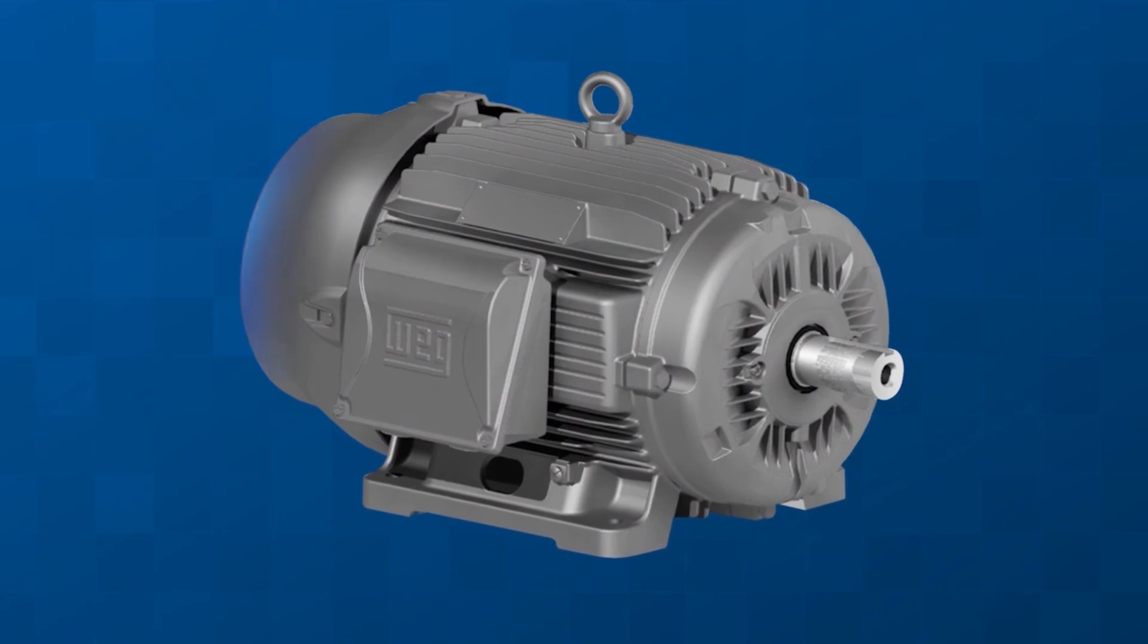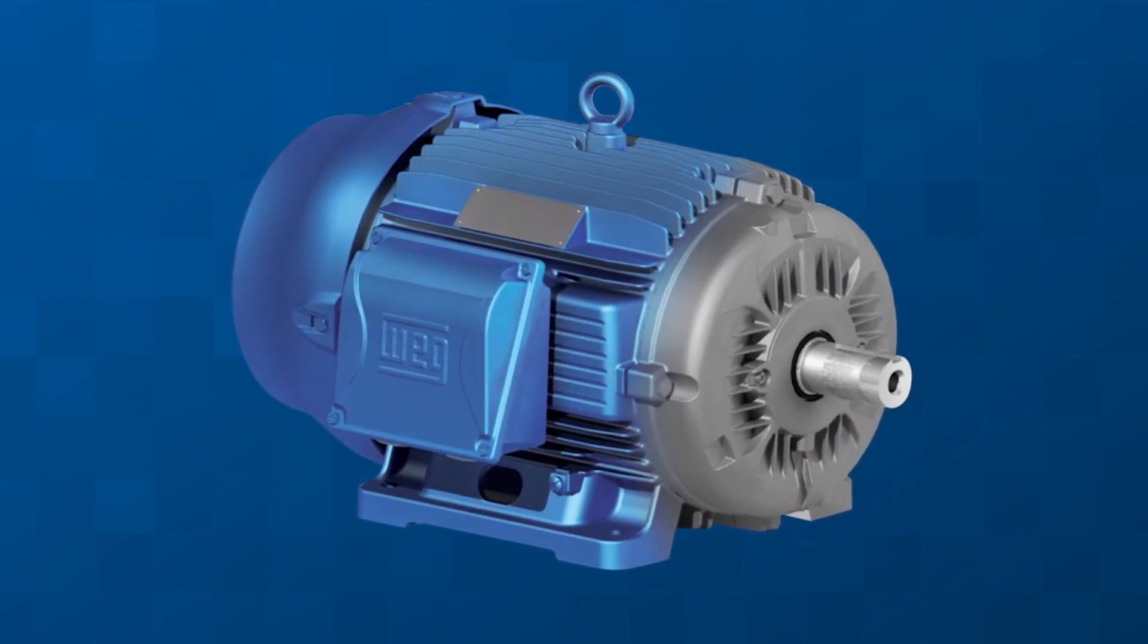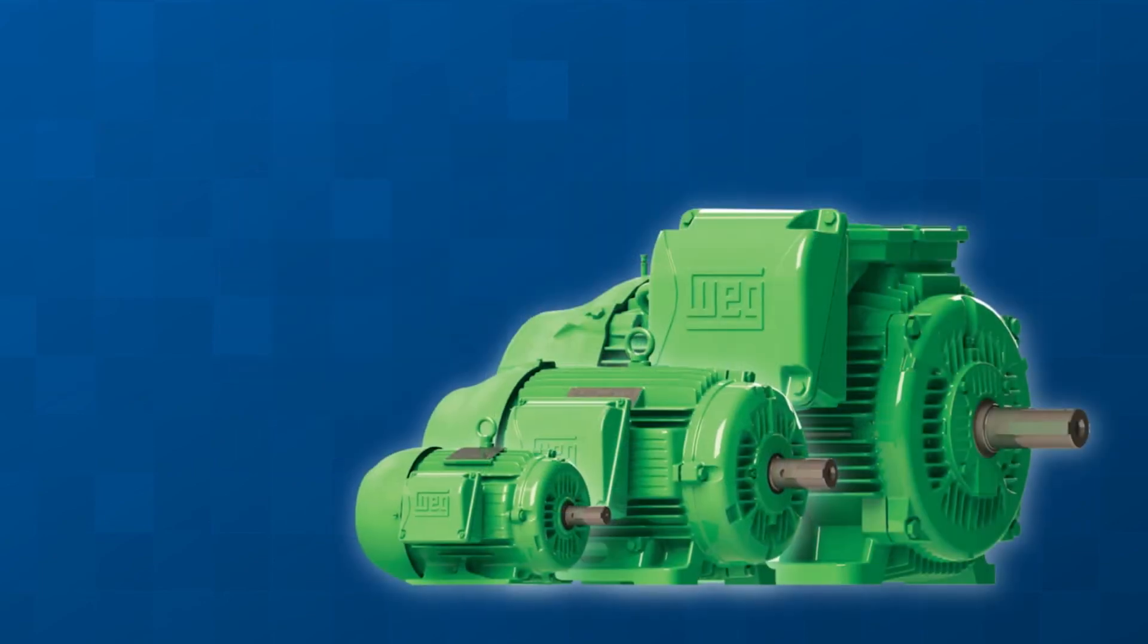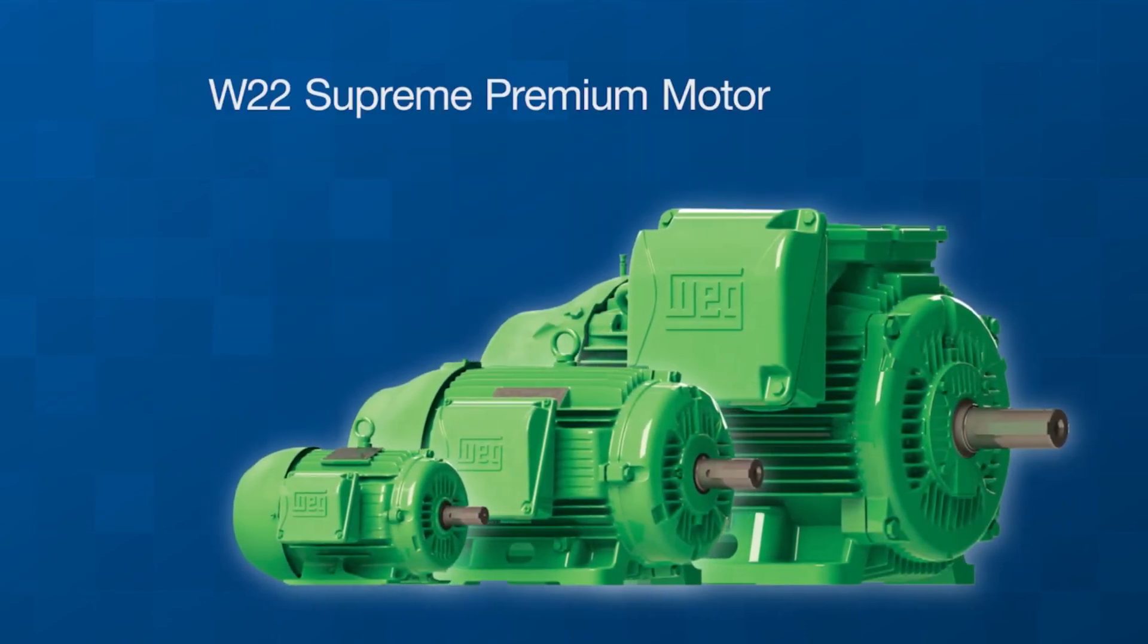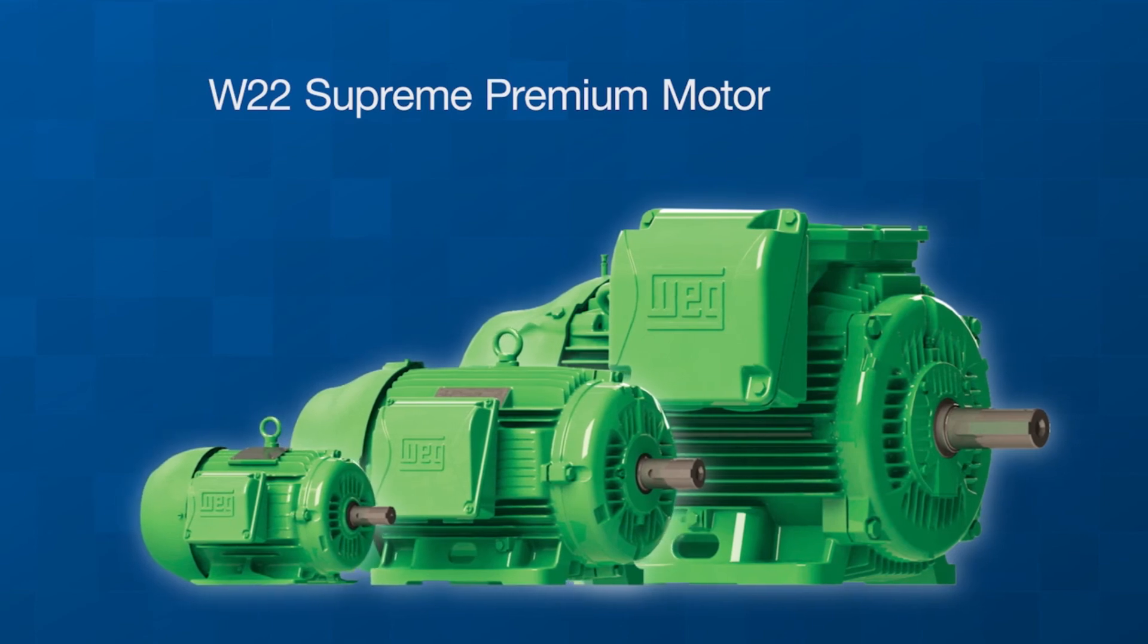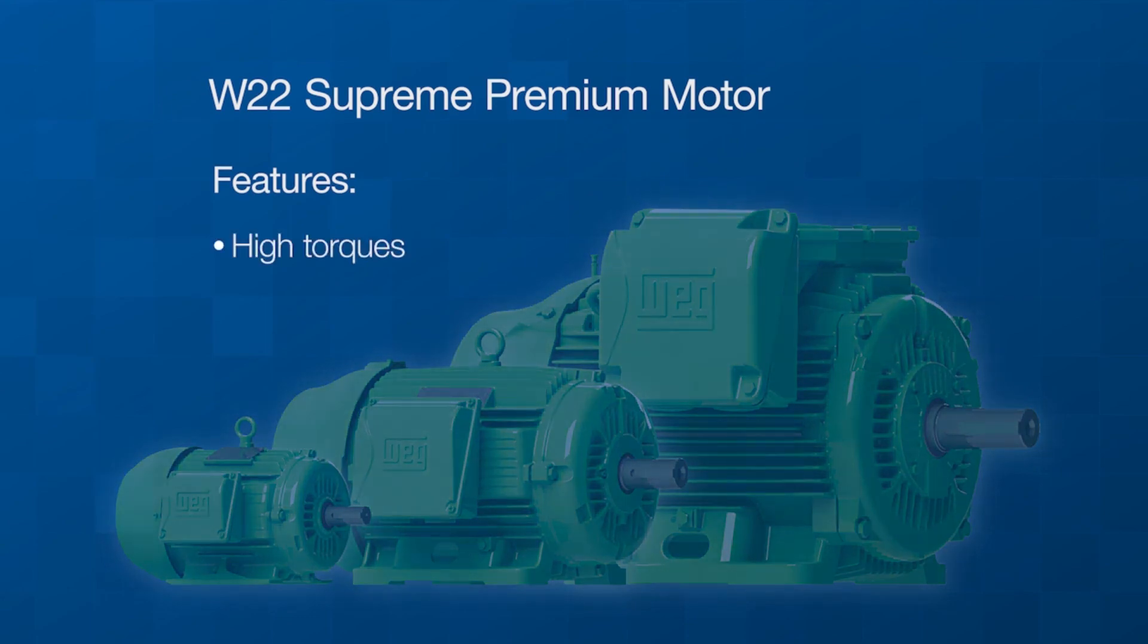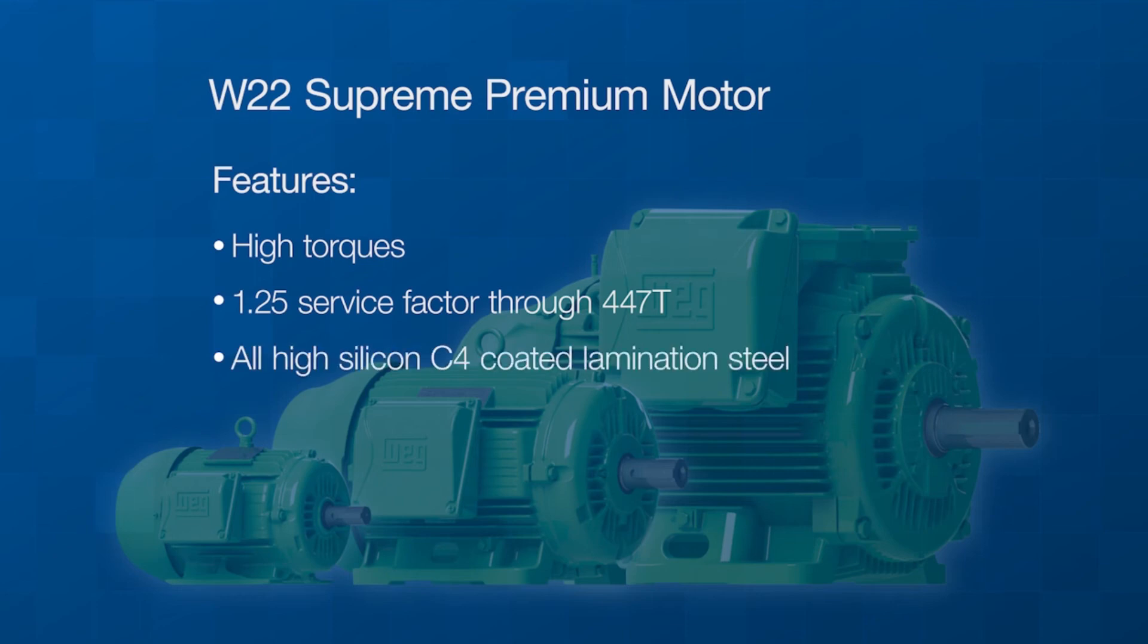The WEG coating paint system exceeds 200 hours in the ASTM 117 salt fog test. For additional energy efficiency, choose a W22 super premium motor, which is two efficiency bands over NEMA premium motors. Key features include high torques, 1.25 service factor through 447T, all high silicon C4 coated lamination steel, low noise, and 50 hertz without derating up to 447/9T.